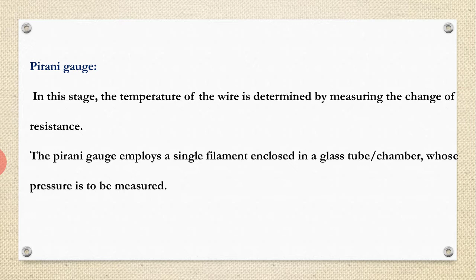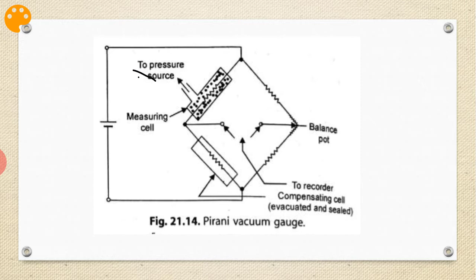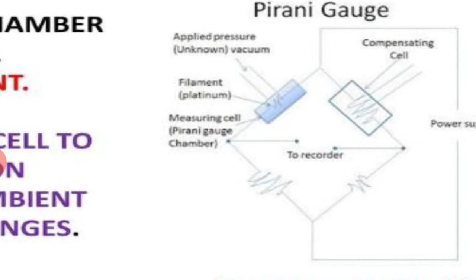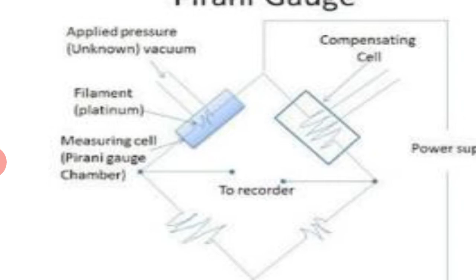So this is the figure which shows the pressure chamber whose pressure is to be measured. We are connecting the pressure source here. This gauge employs a single filament in the form of four coiled wires of tungsten or platinum connected in parallel, enclosed in the glass tube. Further, the Pirani gauge chamber and the compensating cell are housed in a Wheatstone bridge circuit as shown in the diagram.